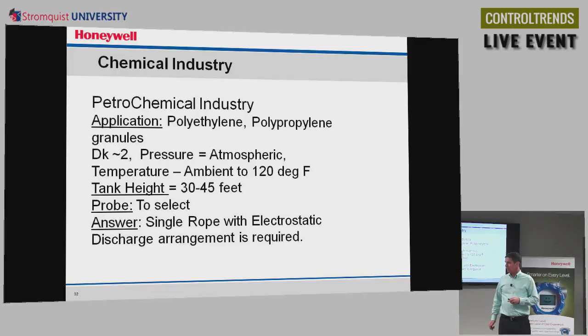Another petrochem industry, this is measuring solids or pellets, and this would be polyethylene or polypropylene granules in a silo, dielectric constant of about 2. So this is solids. The temperature is not a problem, the tank height's fine, but we would typically use a single rope probe, and that would be anchored at the bottom. But remember, the product for the solids application is not available now, and that is of April 2015. That's not in this release.